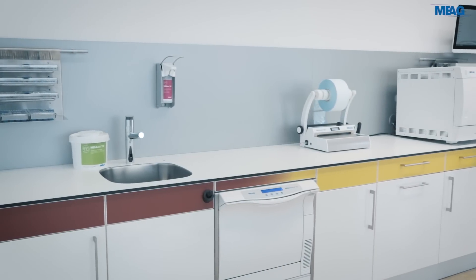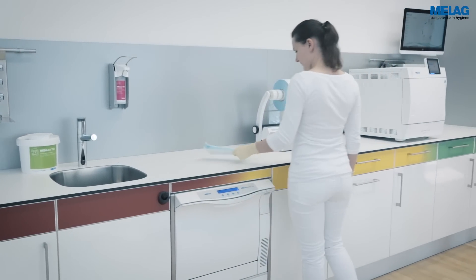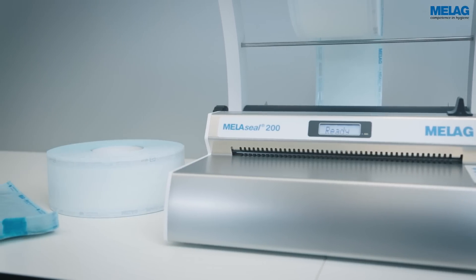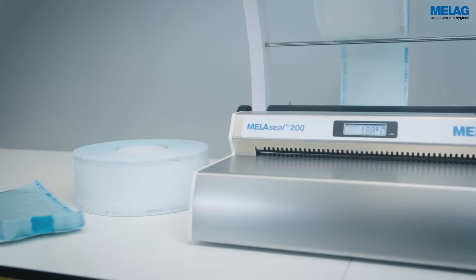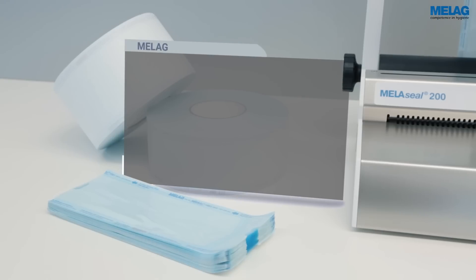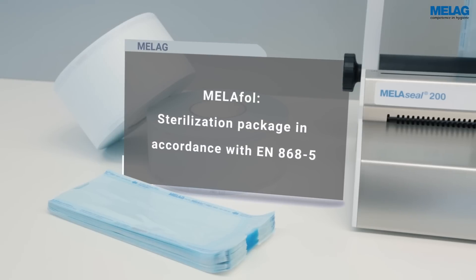The MELAseal 200 sealing temperature is set to 180 degrees. The temperature is optimally adjusted to the use of the MELAfol sterilization packaging. Please comply with the relevant manufacturer's specifications when using a different sterilization packaging.